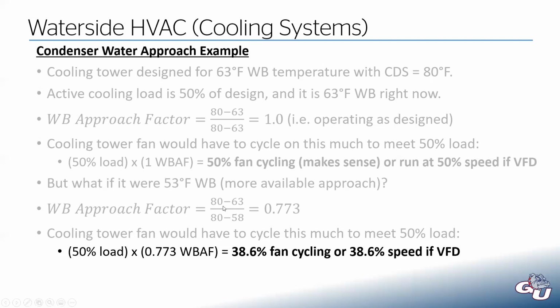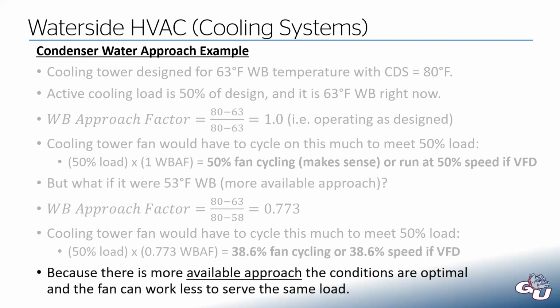You could have a freak day where maybe we designed it for 63-degree wet bulb, but we're at 67. And that will make our wet bulb approach factor greater than 1. And now it's going to have to work even harder. So because we have more available approach, conditions are better, the fan doesn't have to work as hard. And if you're thinking ahead to what this bin calculation might look like, you can probably see what you're going to have to do. You're going to have to figure out how much energy am I going to use at each bin condition based on the active wet bulb temperature.